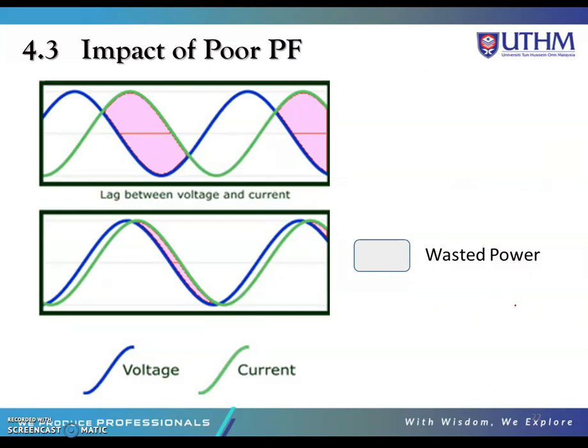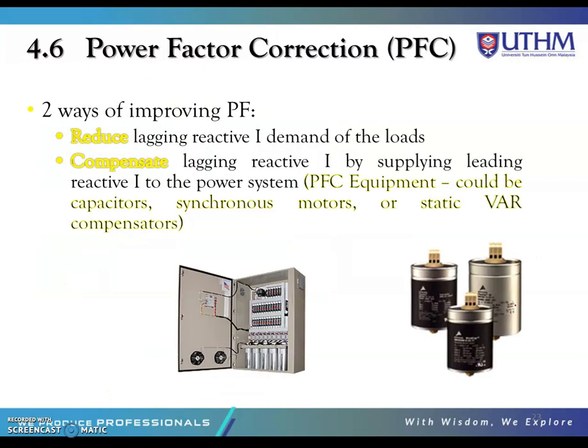The impact of power factor is that there will be a lag between voltage and current, resulting in wasted power. There are two ways to improve power factor: first, reduce the lagging reactive current demand of the loads; and second, compensate for lagging reactive current by supplying leading reactive current to the power system. Power factor correction equipment includes capacitors, synchronous motors, or static VAR compensators.